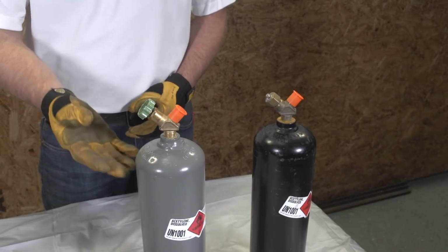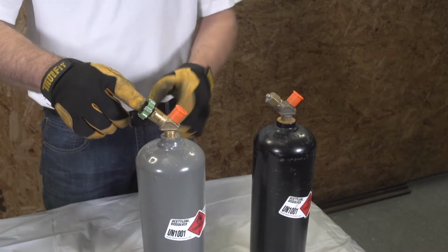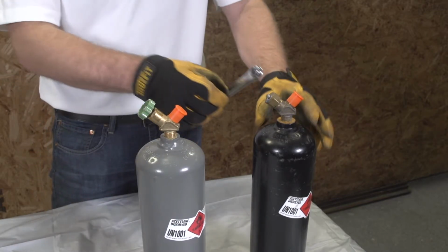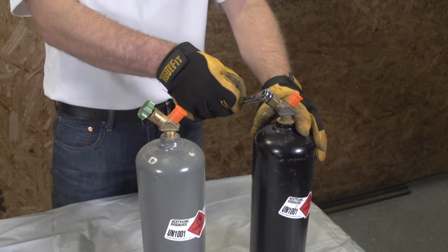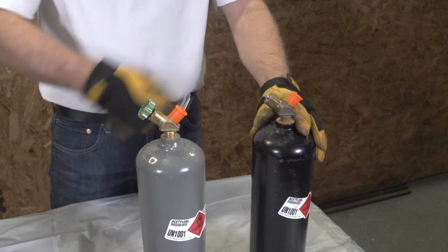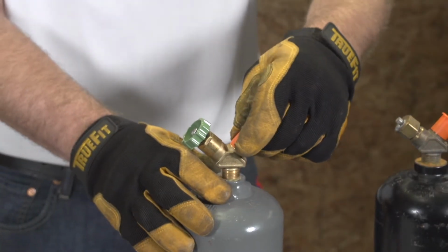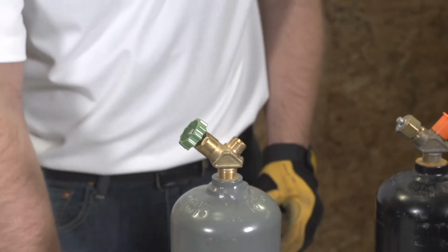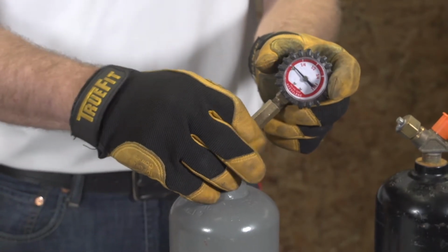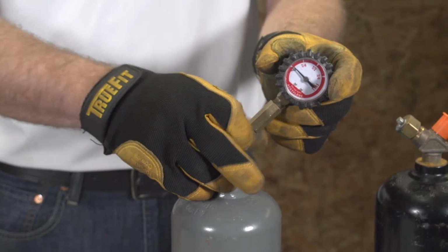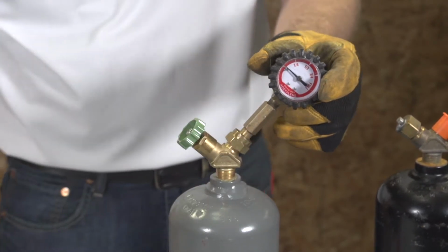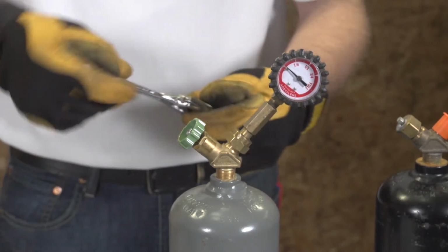Some acetylene valves have a hand-wheeled knob to open the valve. Others may require a valve stem wrench specific for acetylene MC and B cylinders. The pressure ratings on an acetylene cylinder may vary due to a variety of factors, including composition, mass of the filler, and temperature. In fact, acetylene will rise or fall 2.5 psi for each degree of rise or fall in temperature.